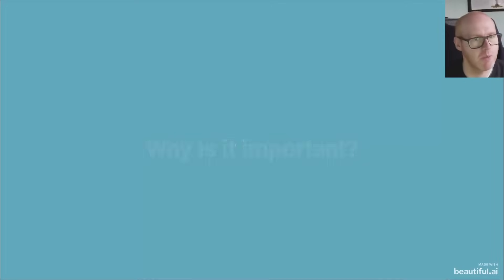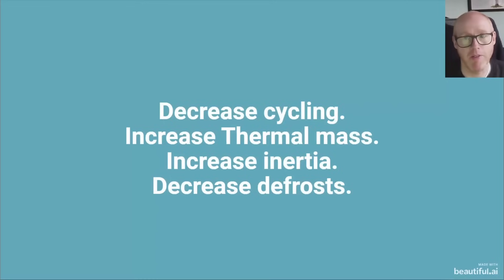So why do we need to think about system volume? You can decrease the cycling because you're increasing the thermal mass, so you're smoothing out those dips and troughs and ons and offs. You're increasing the thermal inertia and you decrease the defrosts, or potentially you can help with the defrost cycle through having sufficient volume.